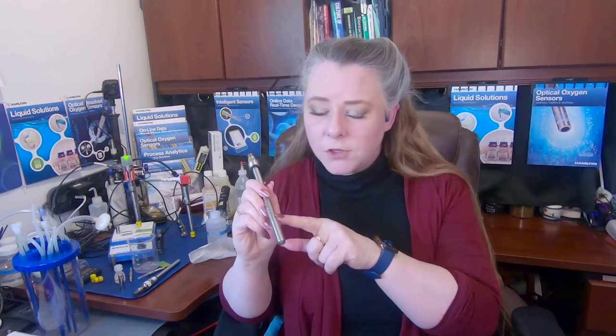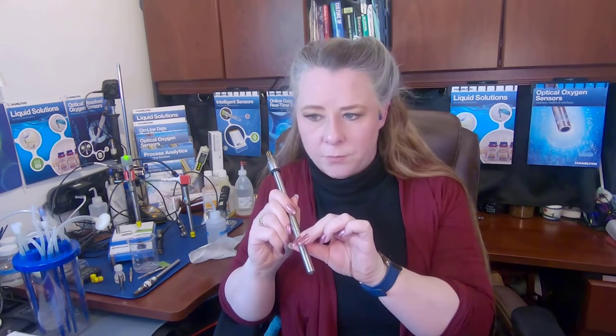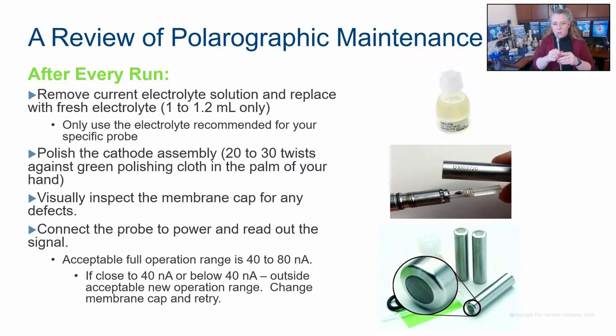Anyhow, you do not want too much liquid in there, because you do not want it to blow up. Blow up is bad. Blow up is expensive. Okay. Once you've visually inspected the sensor cap, added new electrolyte and rinsed it out, and polished your cathode assembly, you're going to hook this probe up to your bioreactor and read a measurement out. It's going to give you a nanoamp signal. Acceptable nanoamp signal ranges are between 40 and 80 nanoamps. You really want to be in the sweet spot, in the middle to the high end.